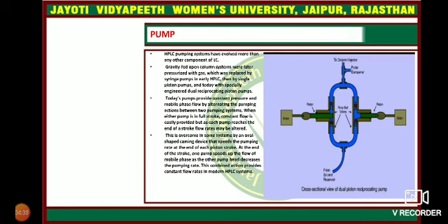When either pump is in full stroke, constant flow is easily provided, but as each pump reaches the end of the stroke, flow rates may be altered. This can be overcome in some systems by an oval shaped cam device that speeds the pumping rate at the end of each piston stroke. At the end of the stroke, one pump speeds up the flow of mobile phase as the other pump head decreases the pumping rate. This combined action provides constant flow rates in modern HPLC systems.